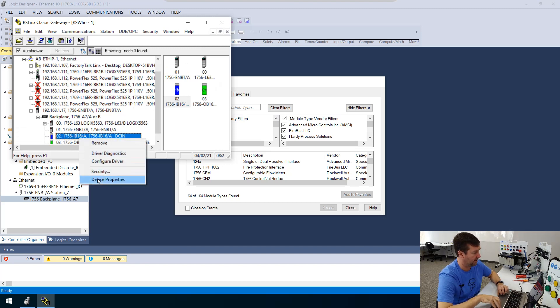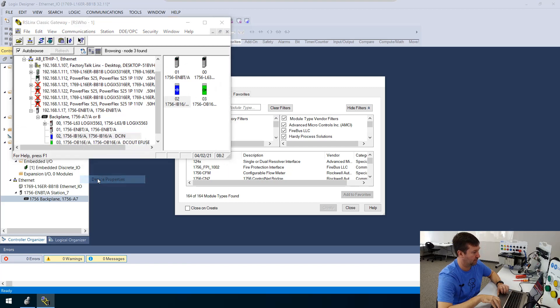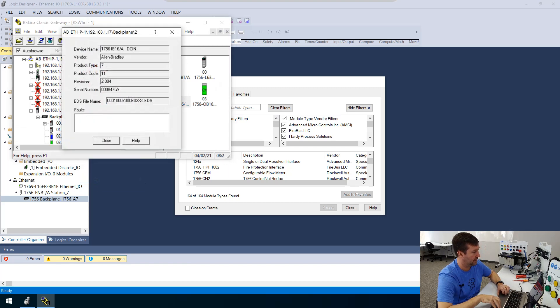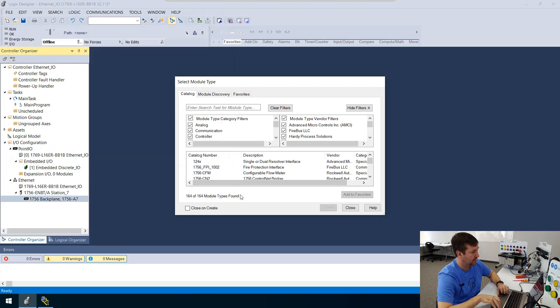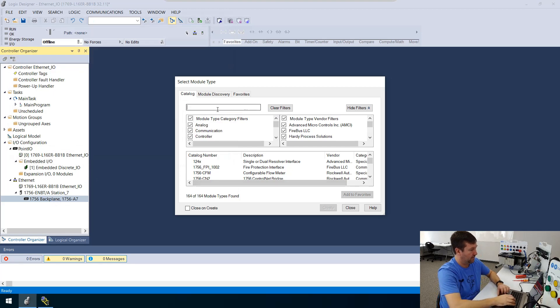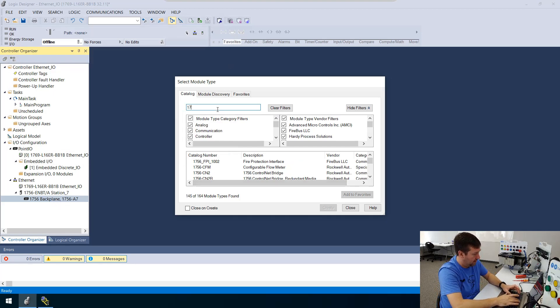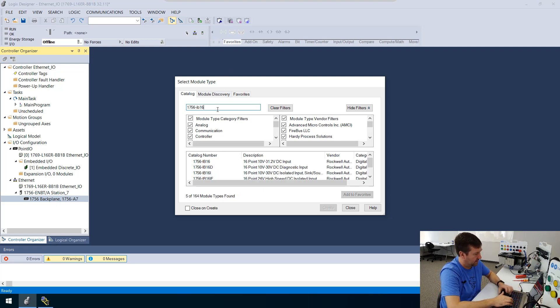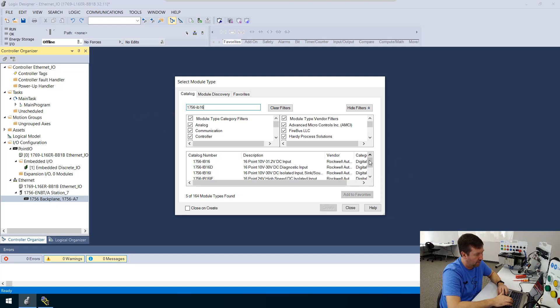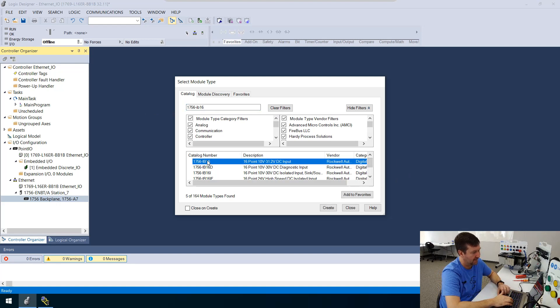slot two is A1756IB16. And I can right click it, device properties, and see that it's 2.004. So let's type in a 1756-IB16. And we've got a few options here, but this was a very basic IB16. So we're going to create it.